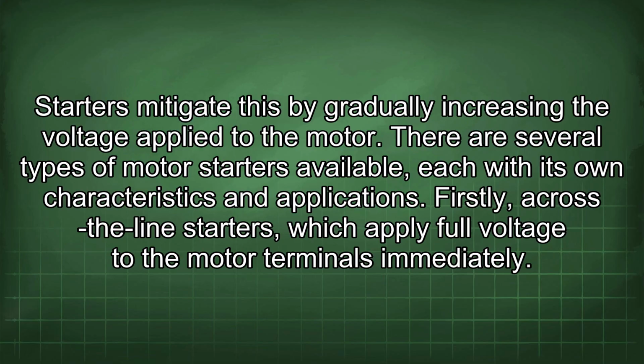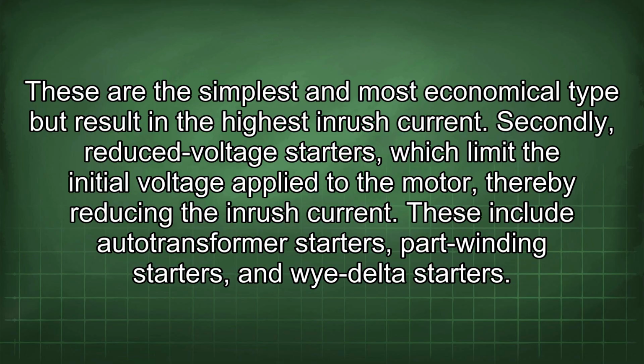Firstly, across-the-line starters, which apply full voltage to the motor terminals immediately. These are the simplest and most economical type, but result in the highest inrush current. Secondly, reduced voltage starters, which limit the initial voltage applied to the motor, thereby reducing the inrush current. These include auto-transformer starters, part-winding starters, and Y-delta starters.